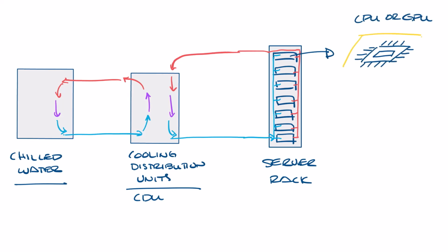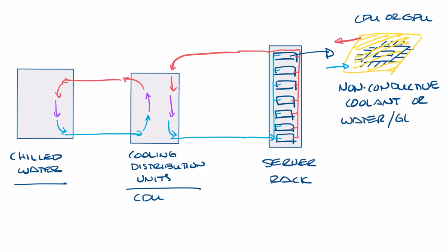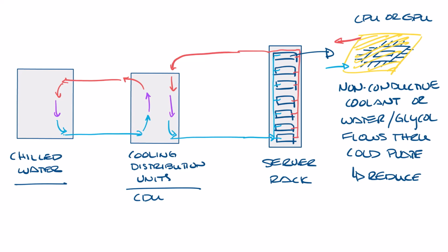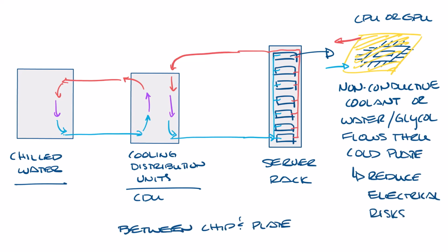Cold plates are mounted on top of the CPU and GPU chips. A non-conductive coolant or water glycol mixture flows through the cold plates, absorbing heat. Non-conductive coolants are used to reduce electrical risk. Between the plate and the chip is a thermal interface material that conducts heat from the chip to the plate.